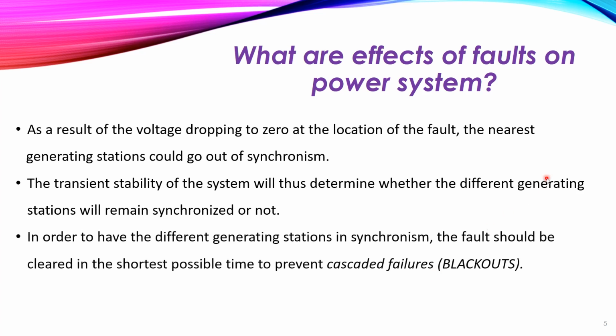In order to keep the different generating stations in synchronism, the fault should be cleared in the shortest possible time. Why? To prevent cascaded failures or the blackout. So what does this mean? It means that we need to clear the fault as fast as possible to prevent the generating power station from going out of synchronism.